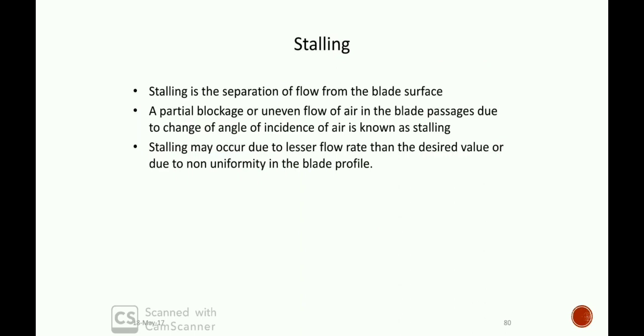Stalling is the separation of flow from the blade surface. It causes partial blockage, allowing uneven flow of air in the blade passage due to a change in the angle of incidence of air. Stalling occurs mainly due to a lesser flow rate than the desired value, or due to non-uniformity in the blade profile.